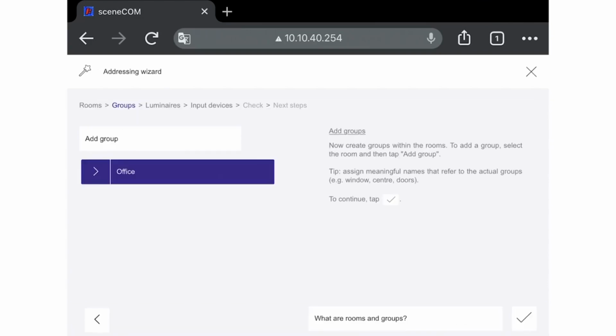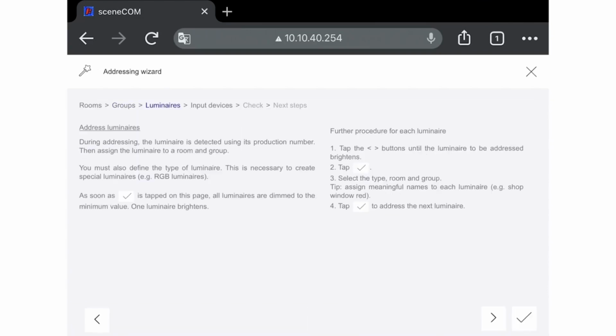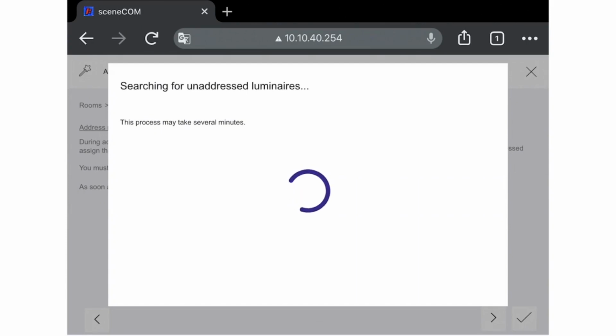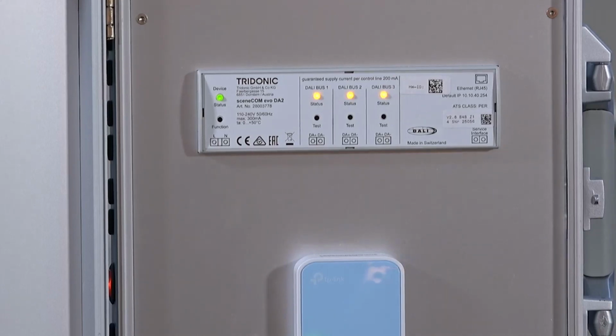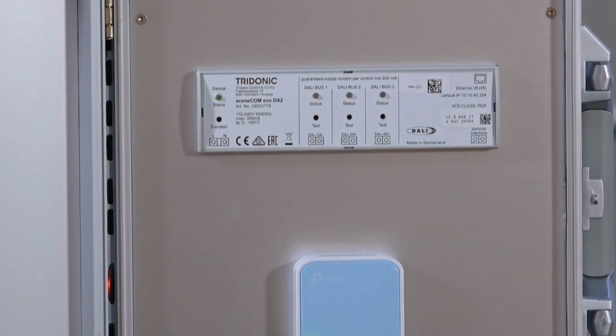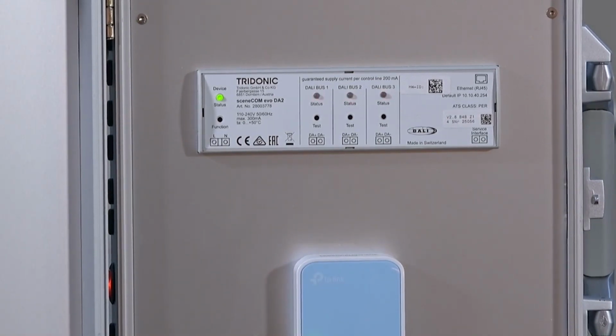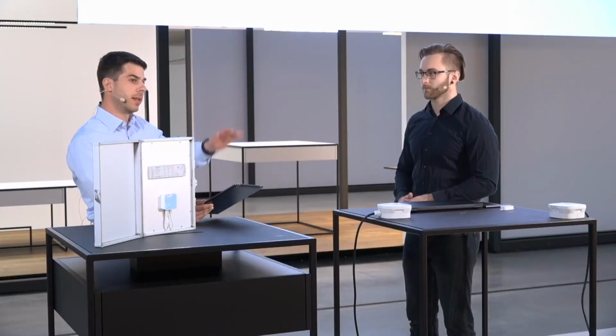Save. Now, with this touch on the check button, it's searching for unaddressed luminaires. So that means, same as if I would have connected wired luminaires, it does exactly the same here for our wireless luminaires. We also see that blinking pattern of the LEDs changed. What does this indicate? This indicates that the DALI controller is searching on its DALI lines.